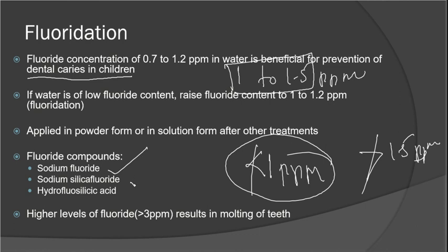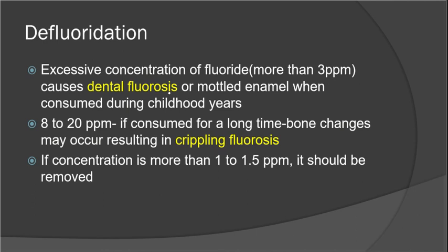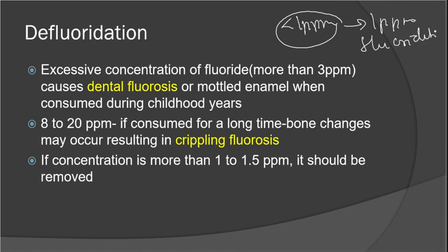If the fluoride concentration is less than 1 ppm, we add fluoride compounds such as sodium fluoride, sodium silicofluoride, and hydrofluorosilicic acid — this process is called fluoridation. If the concentration is greater than 1.5 ppm, it causes mottling of teeth, also known as dental fluorosis, and long-term excess causes skeletal fluorosis. To reduce excess fluoride, we carry out defluoridation.